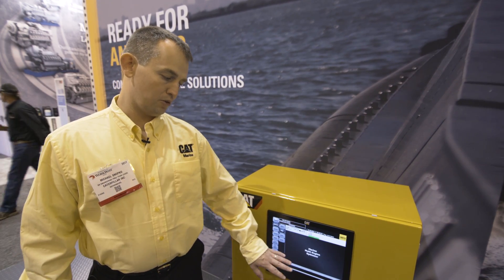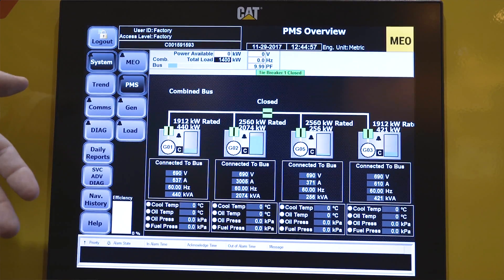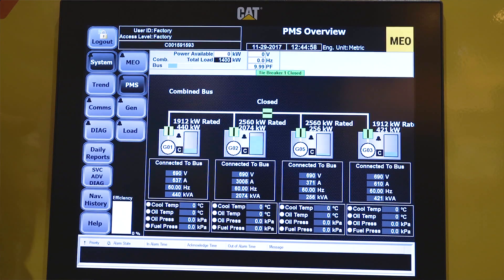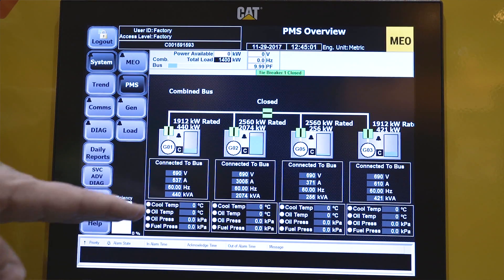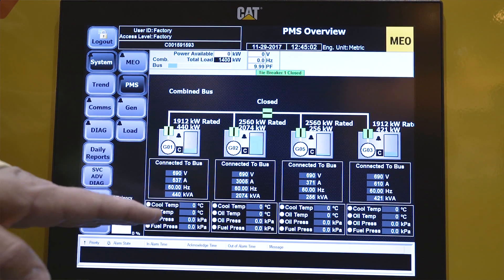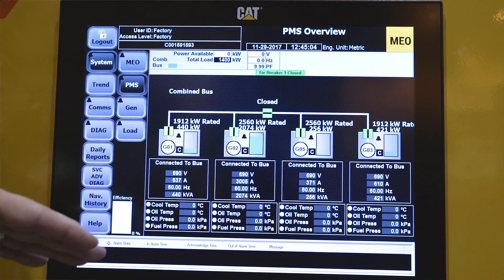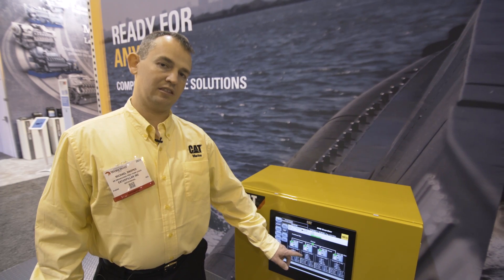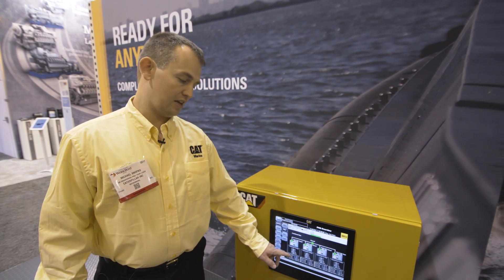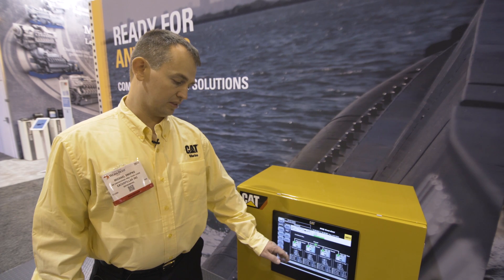We also have our whole system overview, where you can overview the power management system on the vessel. An example here shows a four-engine system with a tiebreaker in the middle, and you can see each generator operating, with different loads indicating the dynamic asymmetric load allocation, which provides some of the fuel savings.